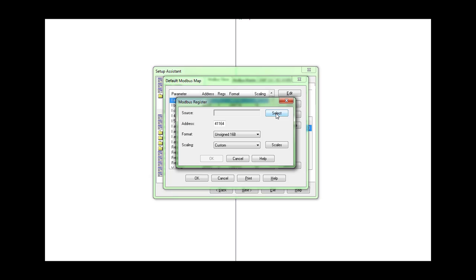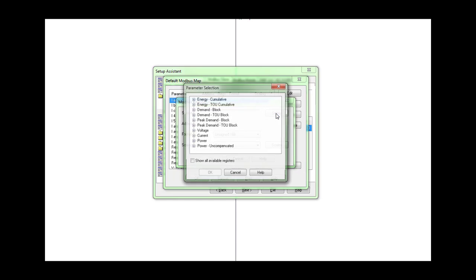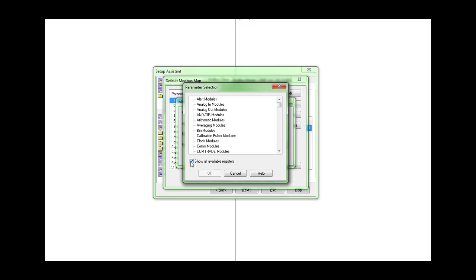So click on Select, and we can see all the available measurements inside the meter. First of all, we see the default or basic ones, but please check the box at the end that allows us to show all available registers. The idea here is to look for the harmonic modules. These modules are organized alphabetically, so we can see the harmonic modules here, and then harmonics for the current and the voltage, per phase.